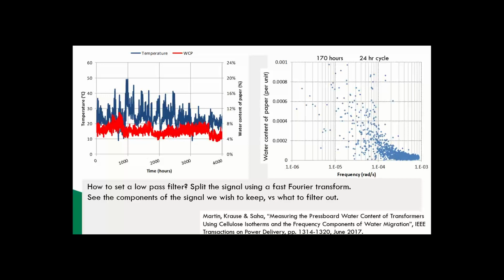So in terms of my graph on the right, what I'm showing is the spectral content of our signal. Now, we get a few points high up around 24 hours. That's where I put on the graph just a 24-hour cycle. So all I'm doing there is taking the signal, doing the fast Fourier transform on it, and we're getting quite a fair bit of signal around the 24 hours. Now, this signal is related to these 24-hour daily changes of the transformer. So we're thinking, let's get rid of these. We don't want that. We're more wanting to be looking at these very slow changes in water content, because I showed earlier the figure where we were showing how these time constants are affected by temperature and also the thickness of the paper.